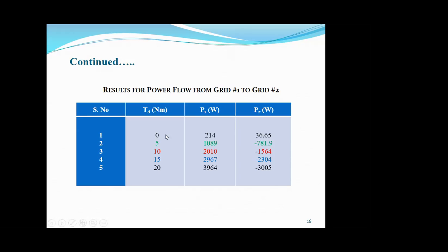When the torque is increased from 0 Newton meter to 5 Newton meter, PS becomes more positive but PR becomes negative. This shows PS was supplying power to PR. As I denoted earlier, minus PR means the VFT is supplying power to the grid, while plus PS means the grid is supplying power to the VFT.